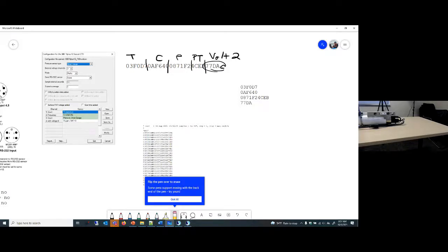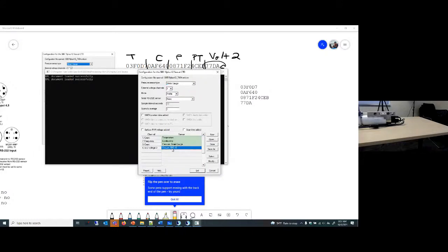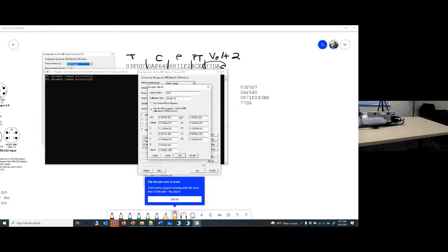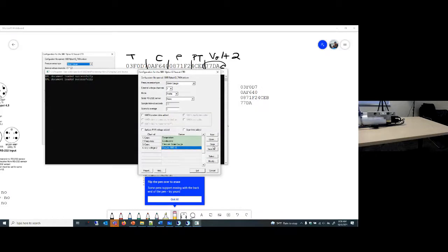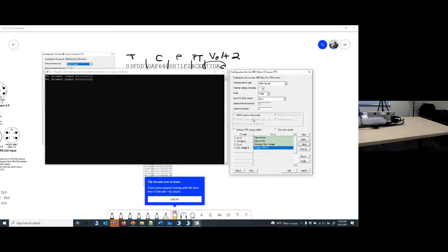So once you've got that in your configuration file, what you want to do is double click on the instrument itself and then load in the calibration coefficients for this particular sensor. And now we can help you with this at Seabird. You don't have to type all of this in manually. If you have a file that contains the calibration coefficients, you can click on the import button, and you'll be able to import the calibration coefficients into this, click OK, and then click Save, and your XMLCon file is ready. What's important to do from time to time is go through and look at the calibration coefficients in your file here and cross-reference those with the calibration certificates you get from Seabird to make sure that these are still correct and the most up-to-date calibration coefficients for your particular instruments.